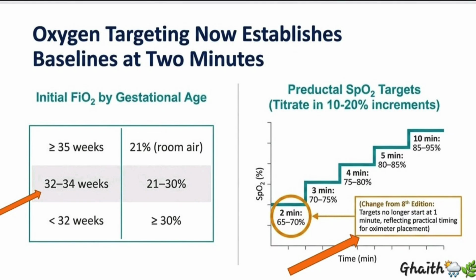The 9th edition shift in the preductal SpO2 target table now establishes baselines starting at 2 minutes to reflect realistic sensor placement. At 2 minutes, the target is 65 to 70%. At 3 minutes, 70 to 75%. At 4 minutes, 75 to 80%. At 5 minutes, 80 to 85%. And by 10 minutes, 85 to 95%.